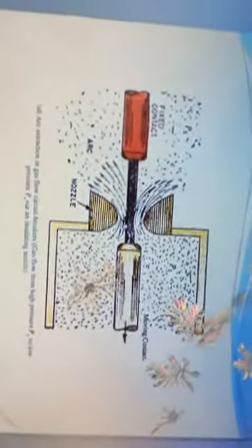Moisture is very harmful to the properties of the gas. In the presence of moisture, hydrogen fluoride is formed during arcing, which can attack the metallic and insulating parts in the circuit breaker. Then, it is an electronegative gas. It does not react with structural material up to 500 degrees centigrade, and regarding products of decomposition during the arc extinction process, SF6 is broken down to some extent into SF4, SF2. These decomposition products recombine upon cooling to form the original gas. So these are the chemical properties.